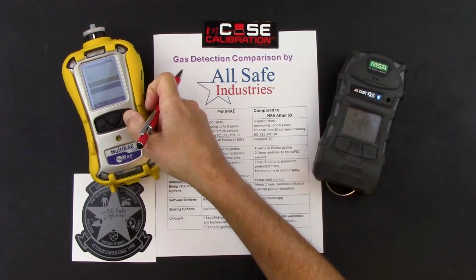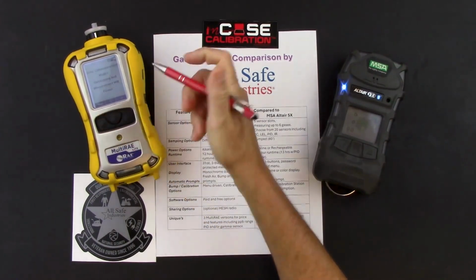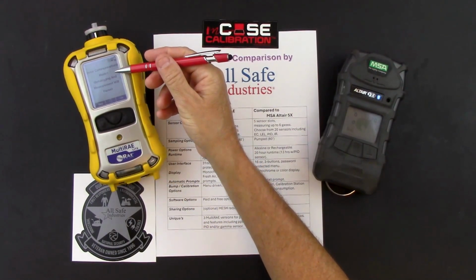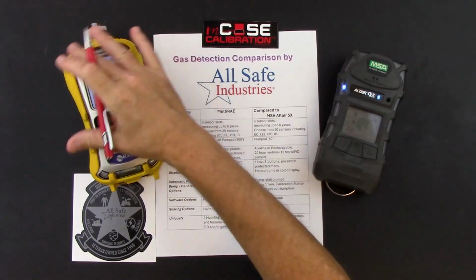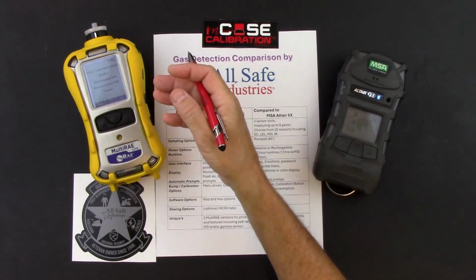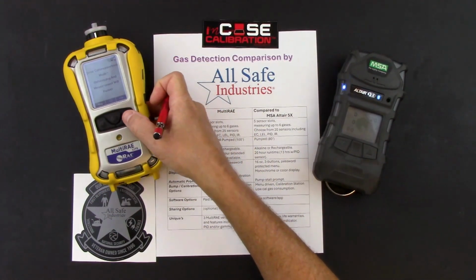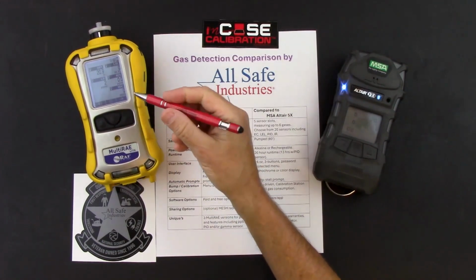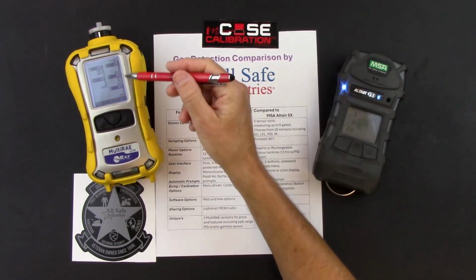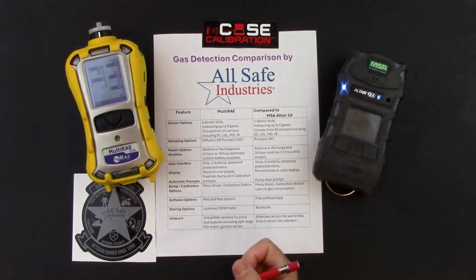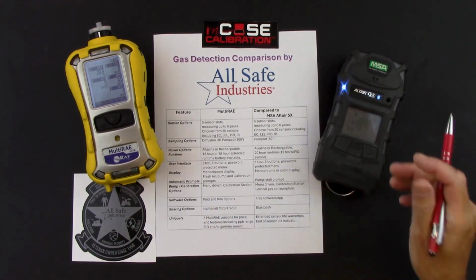If I drop down to exit and hit select, it takes me back to that intercommunication mode screen. And then if I don't do anything, it will eventually come back to the main gas reading screen, or I can just hit the arrow button one more time, and now I'm back to page 1 where I'm getting my gas detection readings.